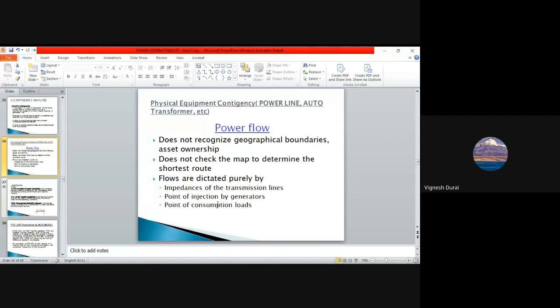Okay. Your contingencies are of two types. One is physical contingency. Suppose equipment fails, or a power line goes into outage, or your auto transformer goes into outage. They are physical equipment contingencies. Power flow does not recognize geographical boundaries or asset ownership. It does not check the map to determine the shortest route. Flows are dictated purely by the impedance of the transmission line, the point of injection by generators, and the point of consumption by the loads. Okay.